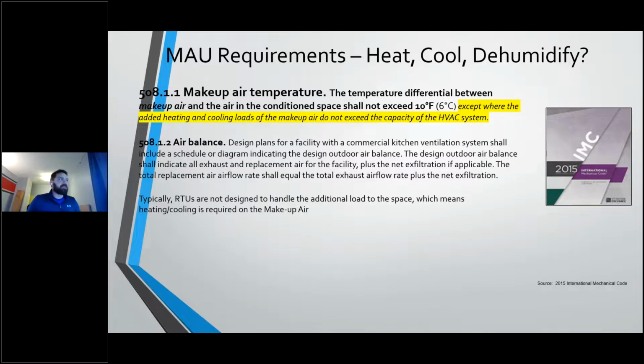So makeup air, 508.1.1 is going to state that the temperature differential between makeup air and the conditioned air in the space shall not exceed 10 degrees Fahrenheit, except where the added heating and cooling load to the makeup air does not exceed the capacity of the HVAC system. What this has historically been taken to mean across the country is that this gives a lot of deference to the engineer. So are we needing to just heat this air and then our rooftop units, our HVAC system, will be able to overcome the hot air and get that air cool? Are we okay with just having a hot kitchen in the summer and a cold kitchen in the winter?